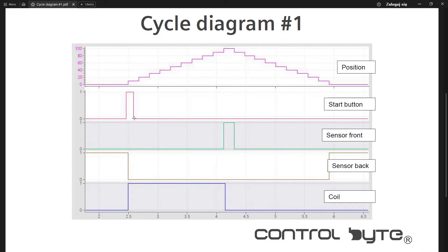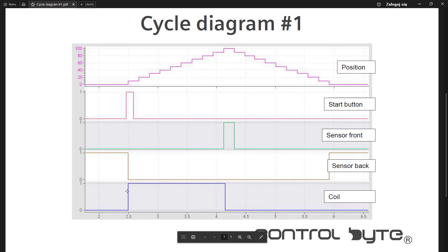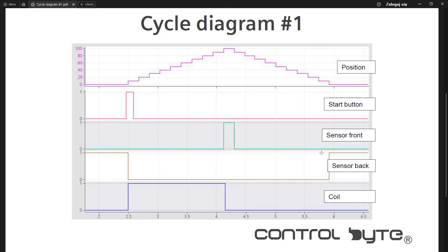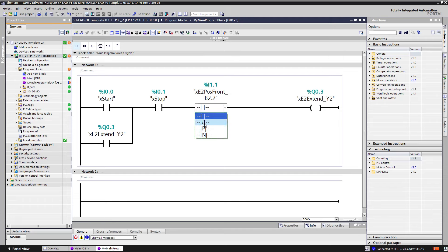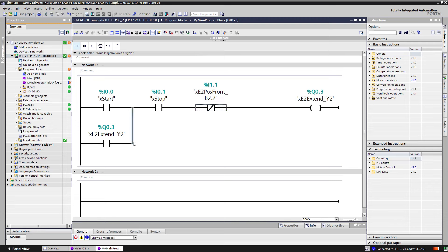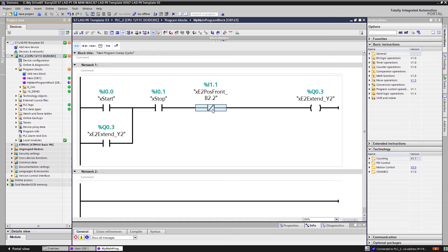So the start button will initiate the cycle. We will use the code with self-hold of the coil. So after activating the coil, the coil will hold itself energized during the cycle. As you can see, all the time the coil is energized, the sensor's signal is in low state. So that means that this contact should be normally closed. It will allow the coil to be energized while the front sensor is not activated. That's how you can decide whether this contact should be NO or NC.